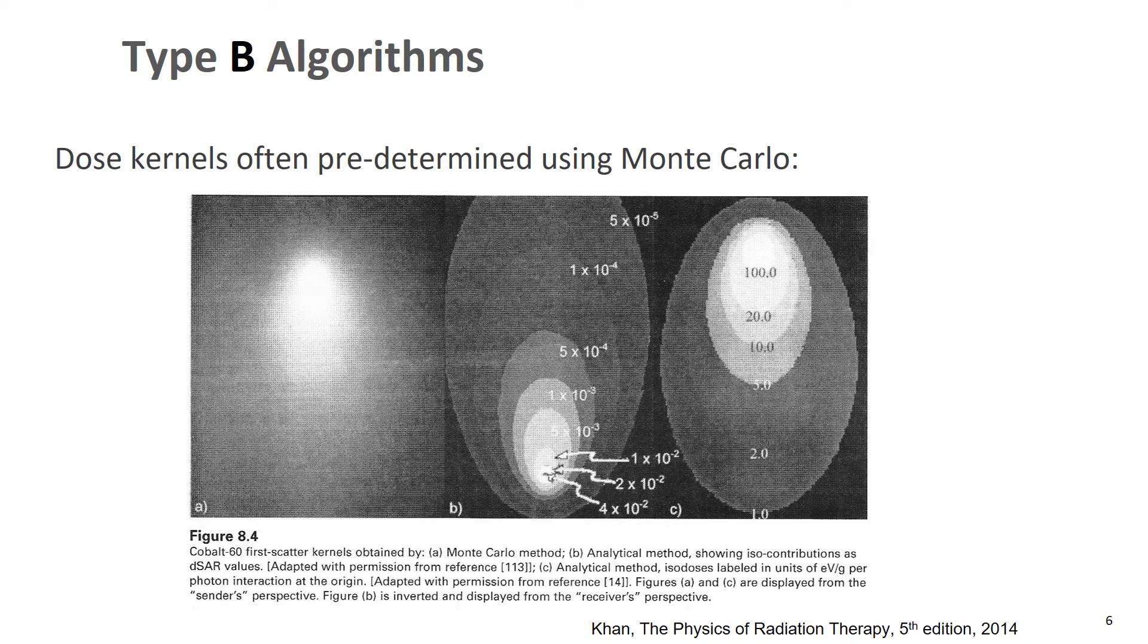These kernels are typically pre-calculated based on complex Monte Carlo simulations. So here's an example in this figure of Monte Carlo derived dose kernels. And so these would be pre-calculated with Monte Carlo, but that doesn't mean that the algorithm itself is a Monte Carlo algorithm. Just the kernel itself is derived using that.